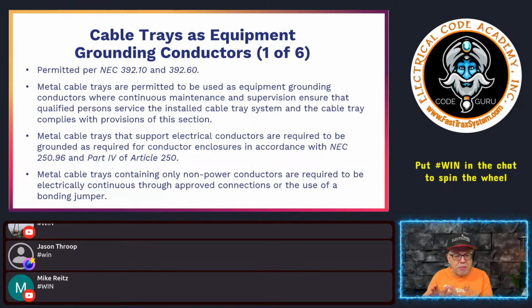This episode is not specifically about cable trays, but about the use of a cable tray as an equipment grounding conductor. And it should go without saying that we're talking about a metal cable tray. Obviously, you couldn't use a plastic one, but you never know, right? All right, let's read what it says here on the screen and follow along. We'll also look at 392.60. This is just use permitted, but we'll definitely look at 392.60. Remember, 392 is the article for cable trays.